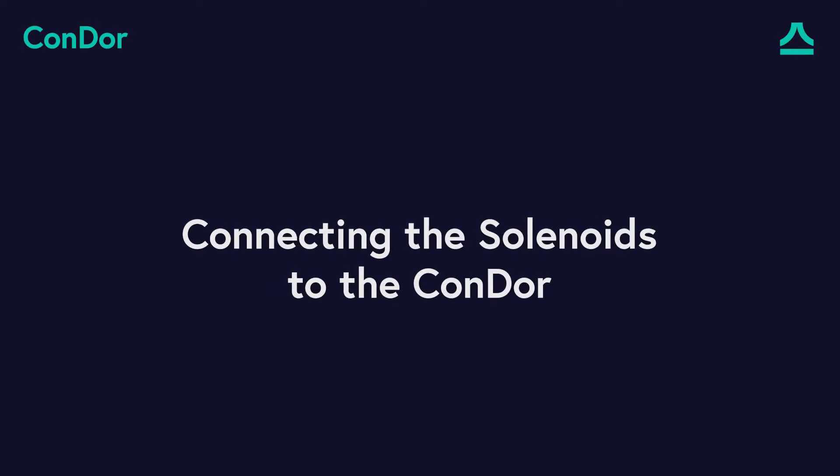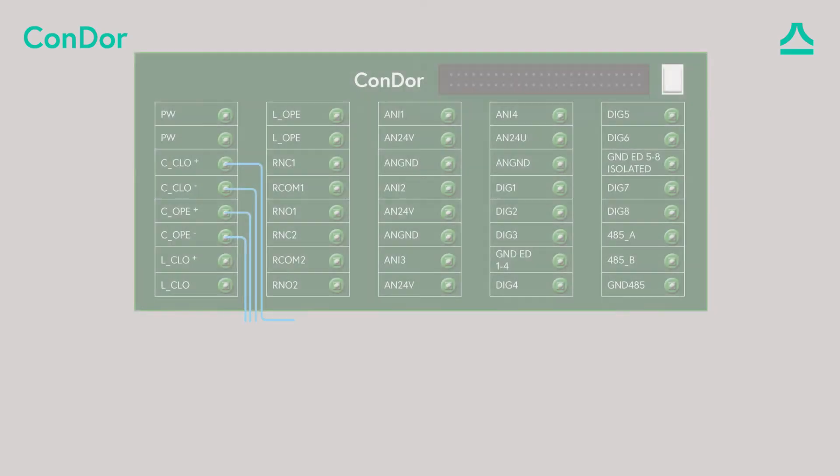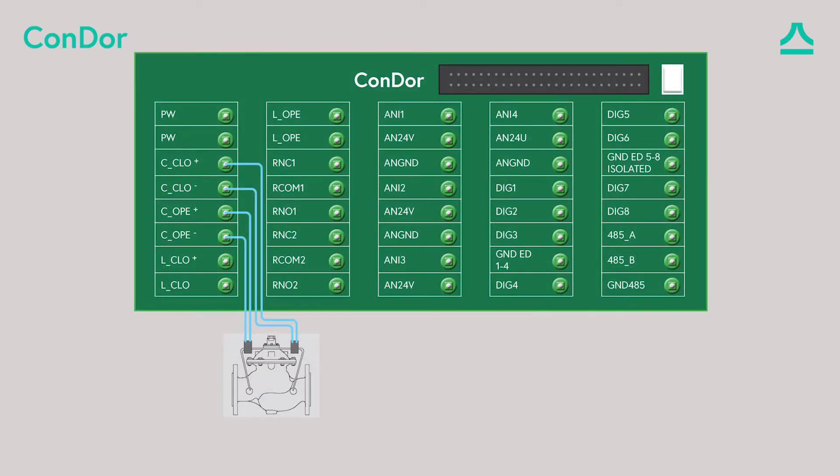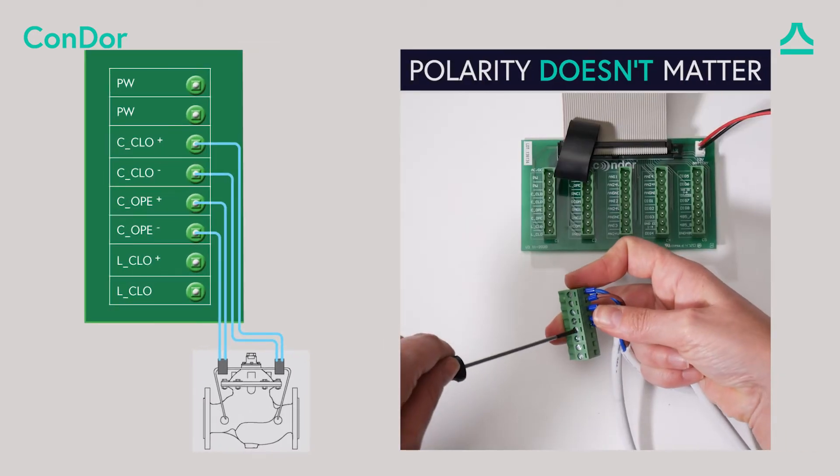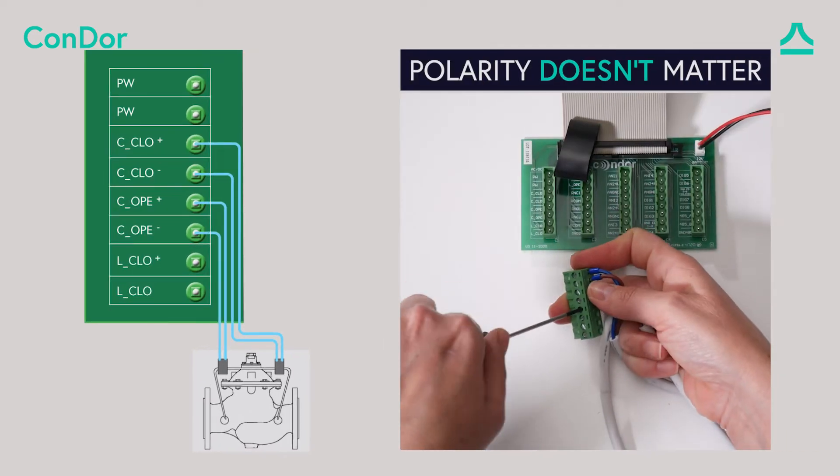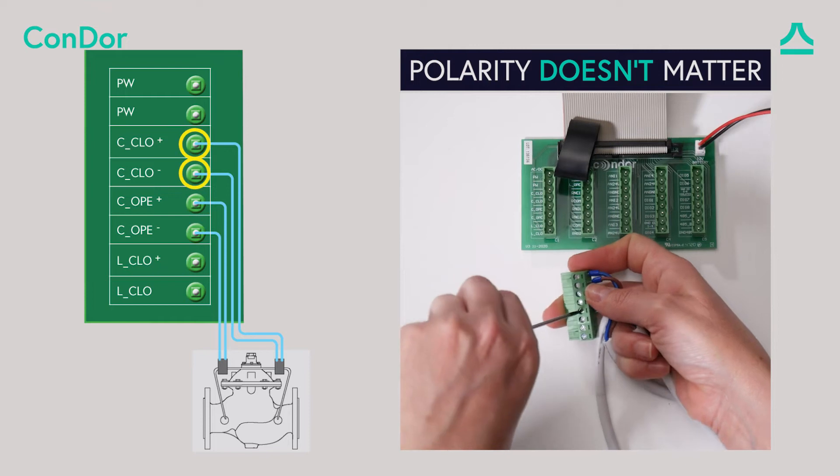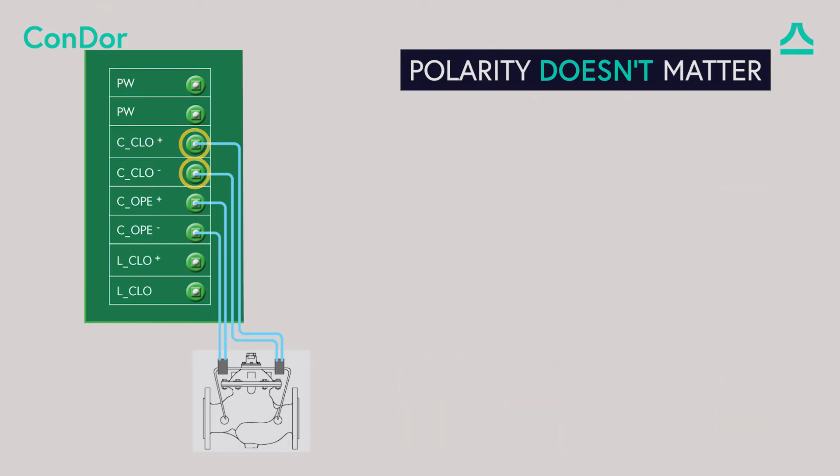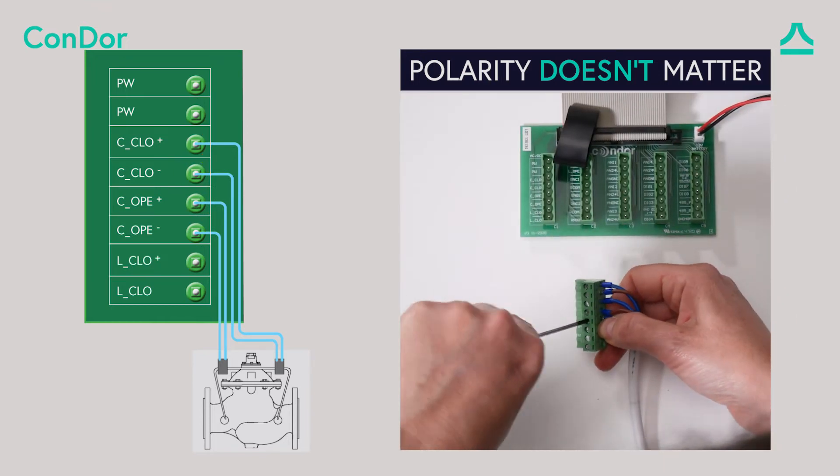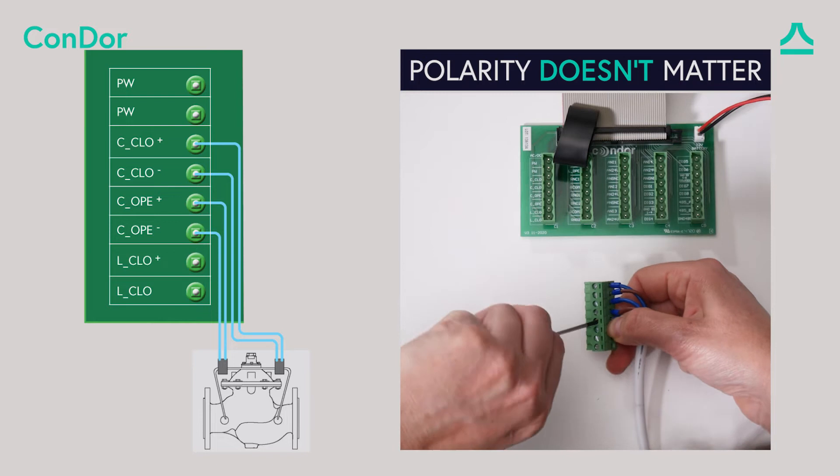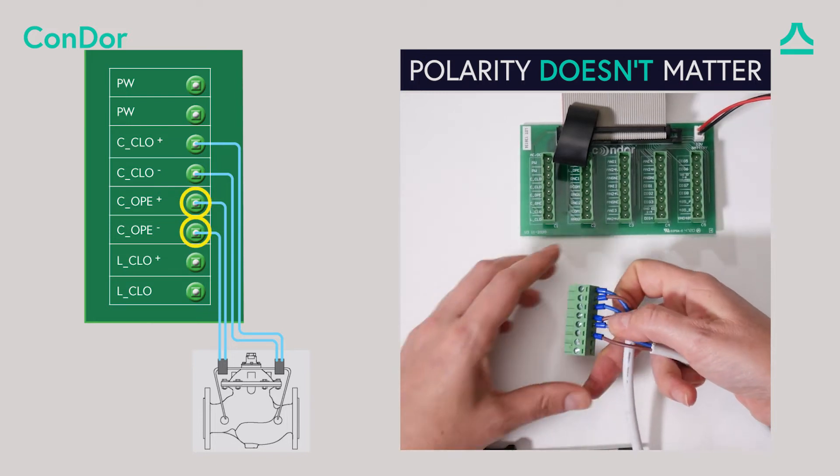Connecting the solenoids to the Condor. The solenoid connects to the Condor with two wires. The closing continuous solenoid valve connects to the C1 connector at port numbers 3 and 4. The opening continuous solenoid valve connects to the C1 connector at port numbers 5 and 6.